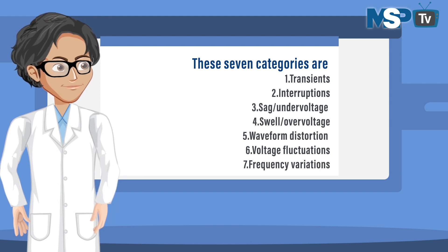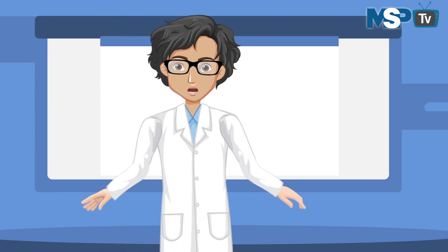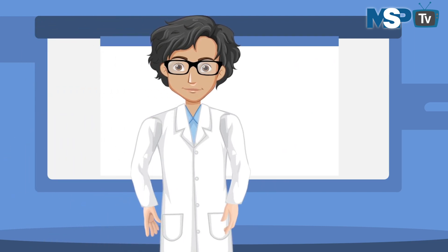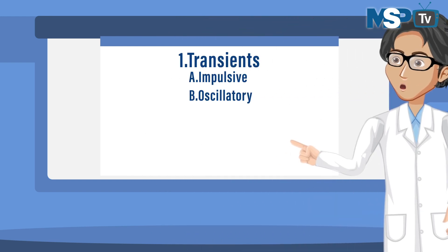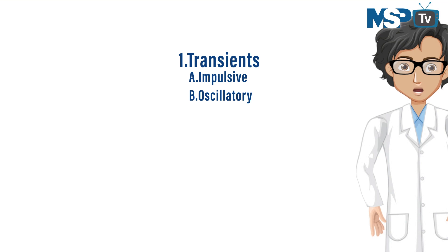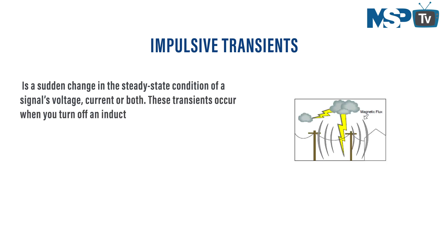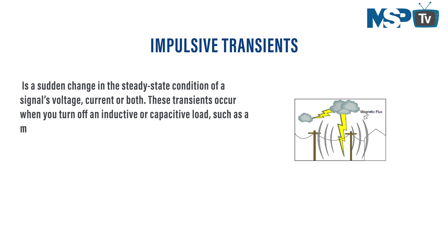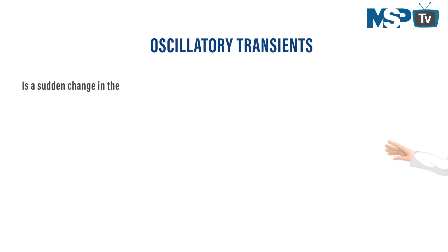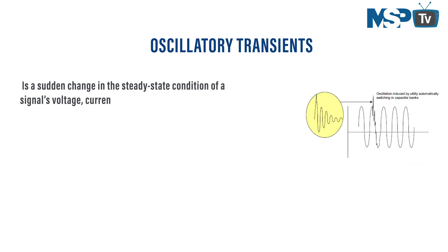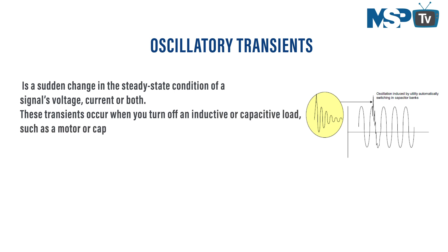Transients are the potentially most damaging type of power disturbance. They fall into two subcategories: impulsive and oscillatory. Impulsive transients are what we commonly call a power surge or spike — caused by lightning, poor grounding, switching of inductive loads, and electrostatic discharge. Oscillatory transients are a sudden change in the steady-state condition of a signal — voltage, current, or both. These transients occur when you turn off an inductive or capacitive load, such as a motor or capacitor bank.